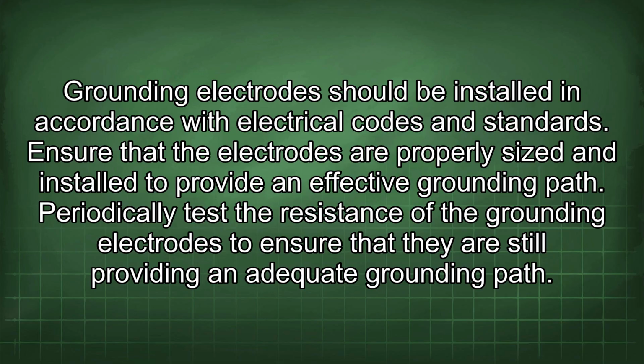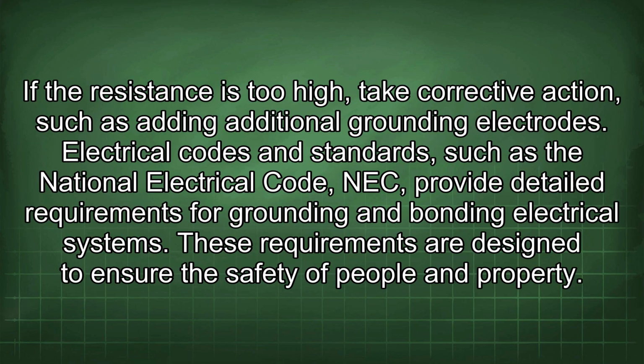Grounding electrodes should be installed in accordance with electrical codes and standards. Ensure that the electrodes are properly sized and installed to provide an effective grounding path. Periodically test the resistance of the grounding electrodes to ensure that they are still providing an adequate grounding path. If the resistance is too high, take corrective action, such as adding additional grounding electrodes. Electrical codes and standards, such as the National Electrical Code (NEC), provide detailed requirements for grounding and bonding electrical systems. These requirements are designed to ensure the safety of people and property.